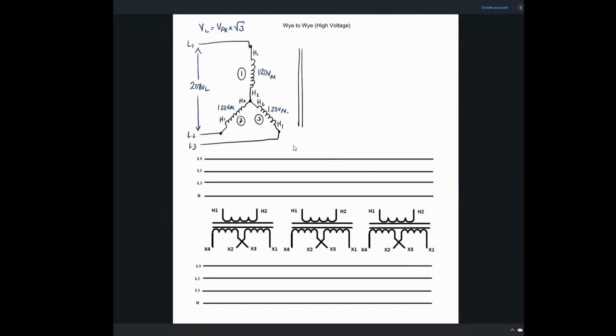Primary is identical. So if you want to pause the video right here and do your diagram for the primary, it's identical. We're having the three lines coming in. They're each feeding H1, right? And we said we're labeling these guys A, B, and C on each of our diagrams. Okay, and H1 was being fed from line 1. H1 on the second transformer was being fed from line 2, and H1 on the third transformer is being fed from line 3. So what I'll do is I'll do the same here, where the neutrals are going to be tied together. So all of the H2s are going to be tied together.